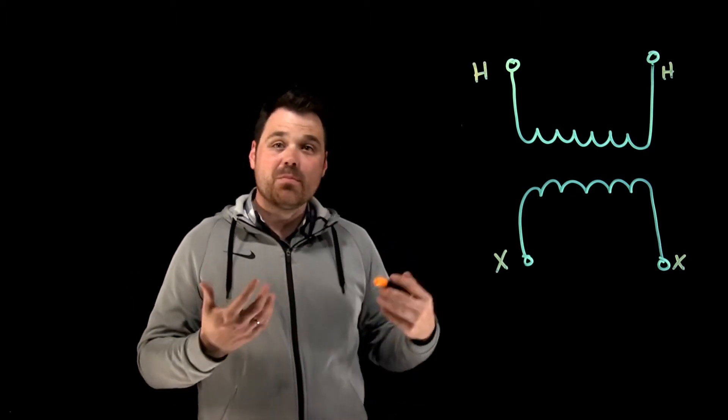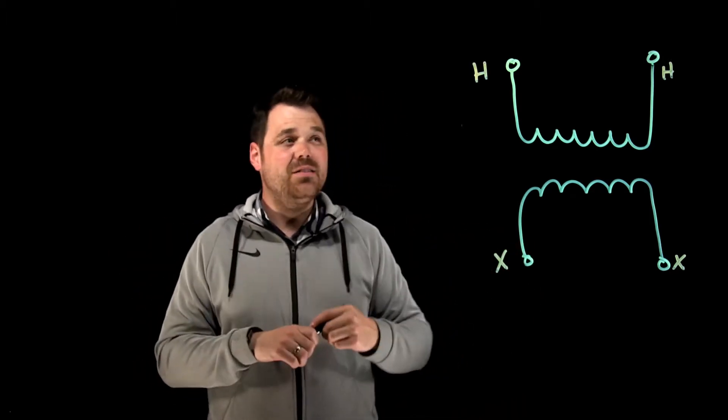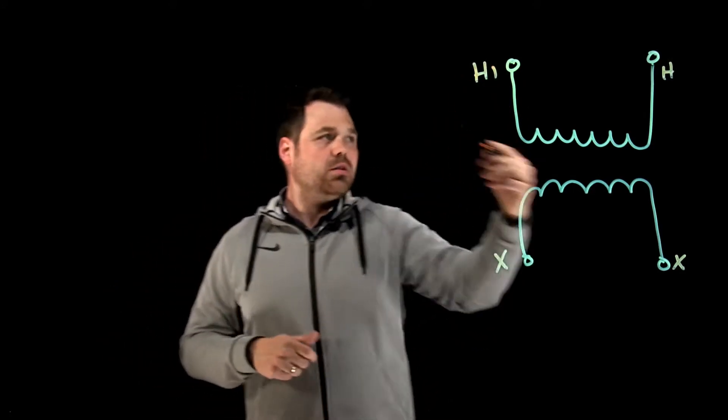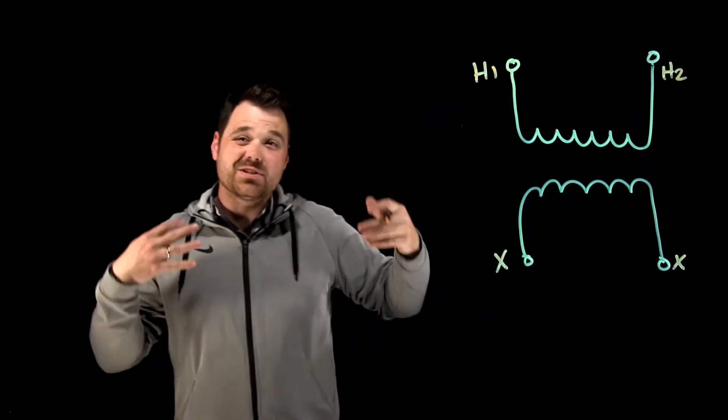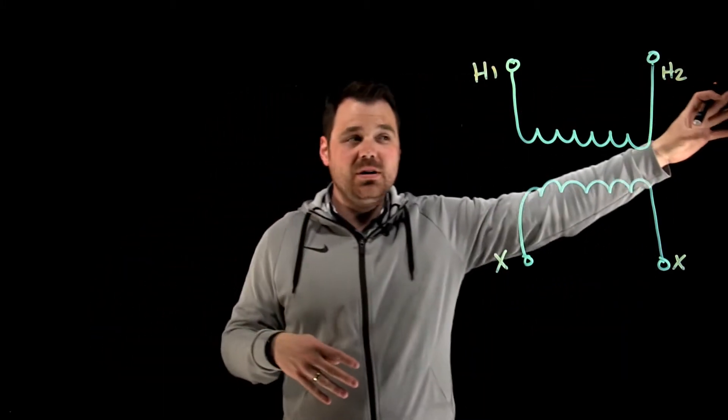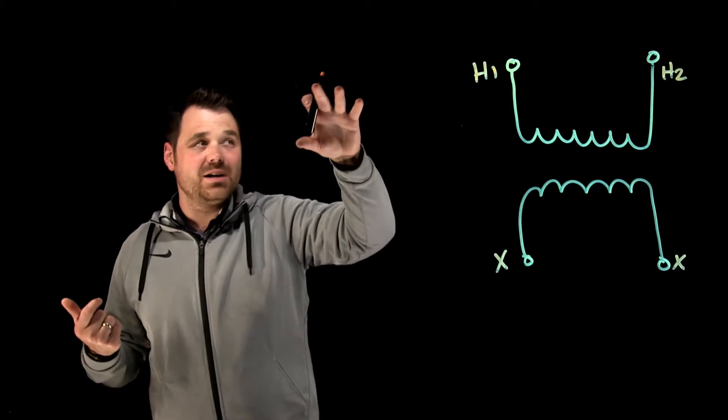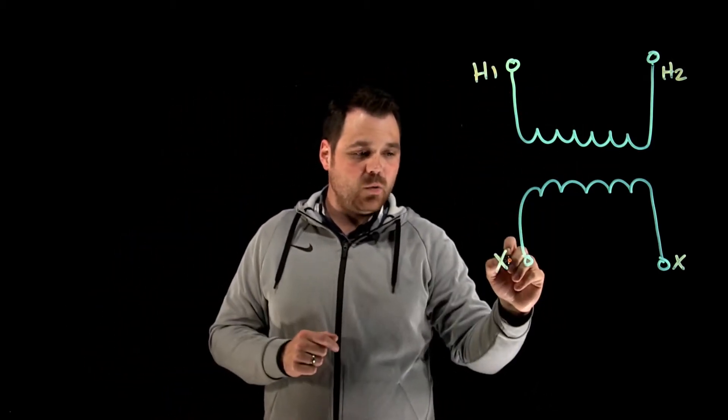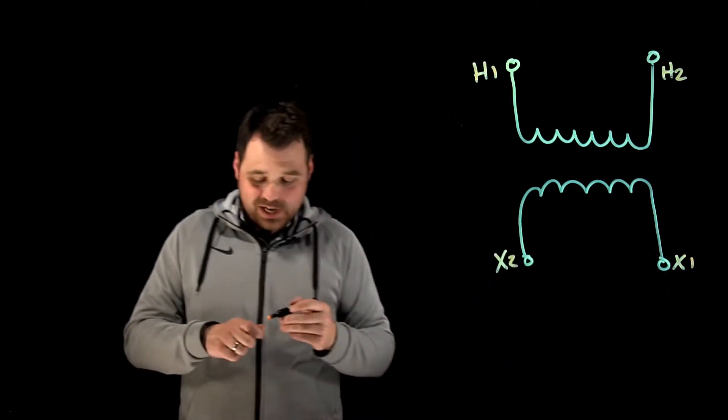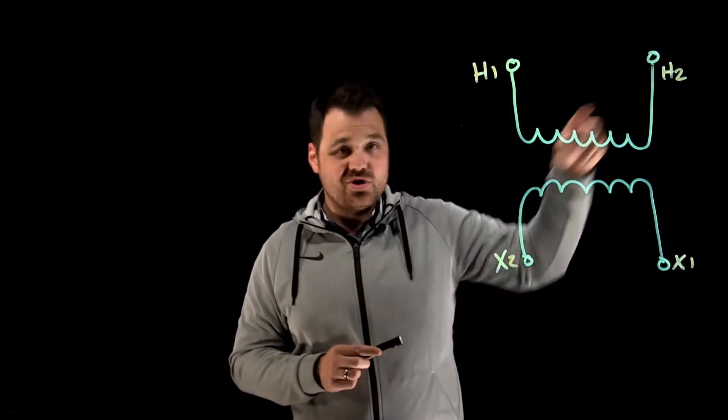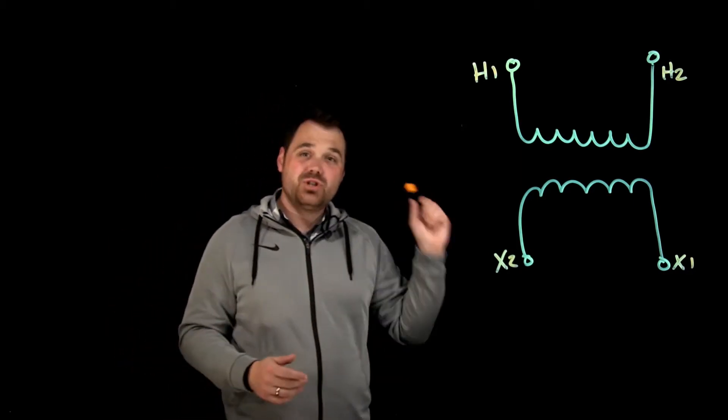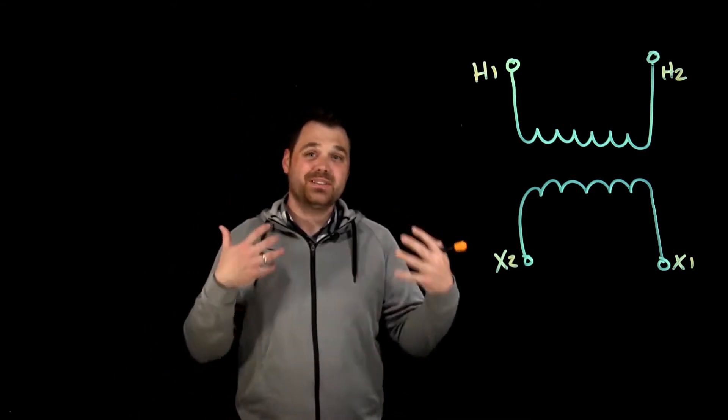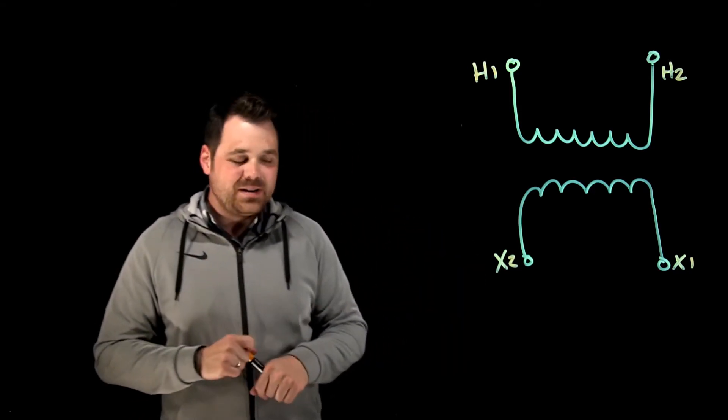They're also going to have numbers because each terminal is identified. H1 will typically be in the top left when you're looking at a drawing. The other side of that winding is H2. If it's a multi-winding transformer with multiple windings on the high side, it'll be H1 through 4 or 6 or whatever. Down lower, we have X1 and X2. Often, you'll see them in the opposite corners, and there's a reason for that which you can check out in the video up above. It has to do with the polarity of the windings.